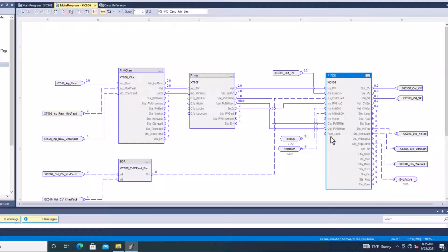If you had 3 elements in front of this and you're summing it up, then you would put something like 0.333, you know, a third of what you're doing. If you have 2, you would put it into halves. So in the instance of 2, you would have the P set ratio at 0.5, right? So that way it could correct the ratio based upon your input of the cascade.